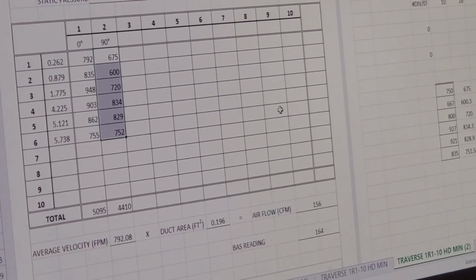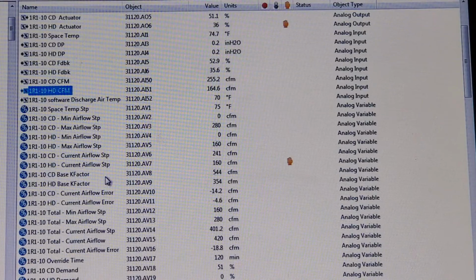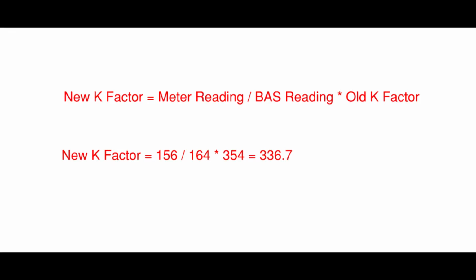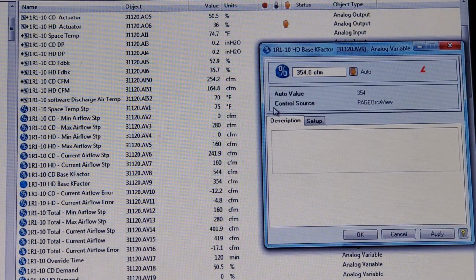So once you have all your data in and you have your two readings, the BAS reading and your reading, then you can go ahead and calculate what your new K factor is going to be. So this is the formula. It's the meter reading over the BAS reading times the old K factor. Now this can change based on the control program that you're using, but for us, this is the equation, and generally this is the equation for most of them. So putting the numbers in, 336.7 is the new K factor.